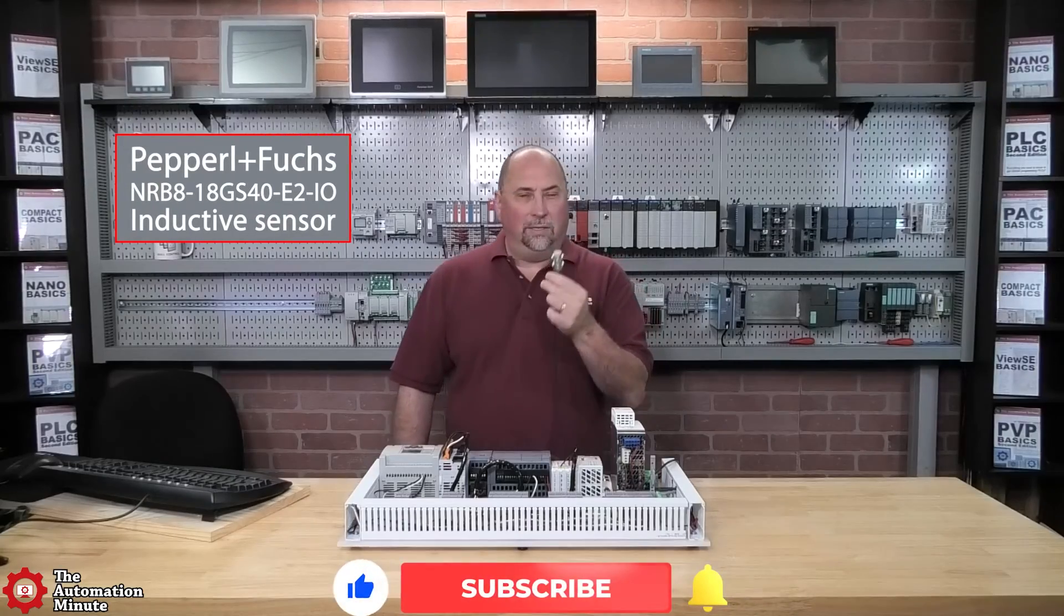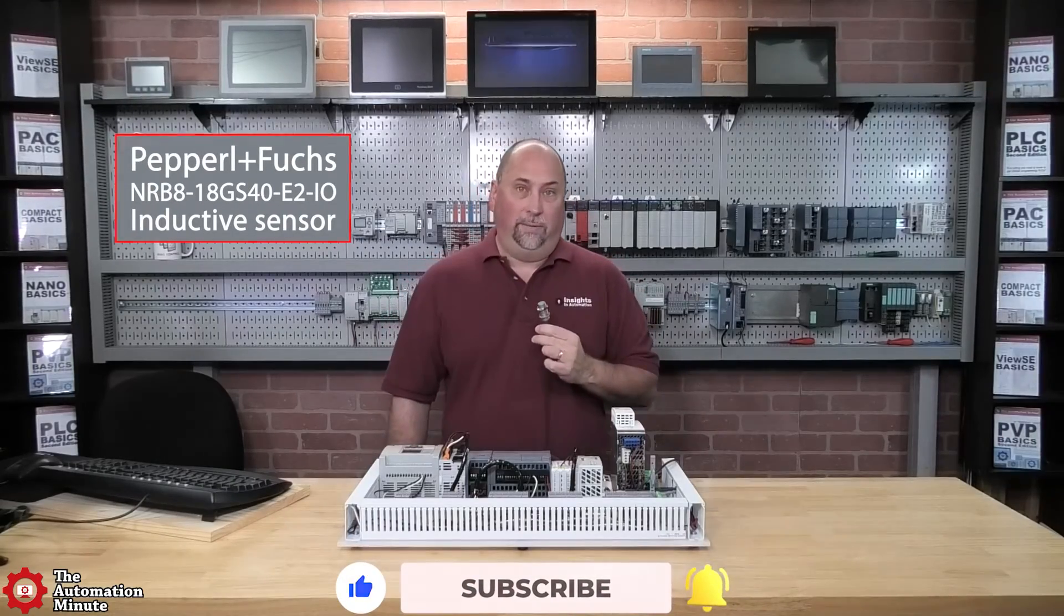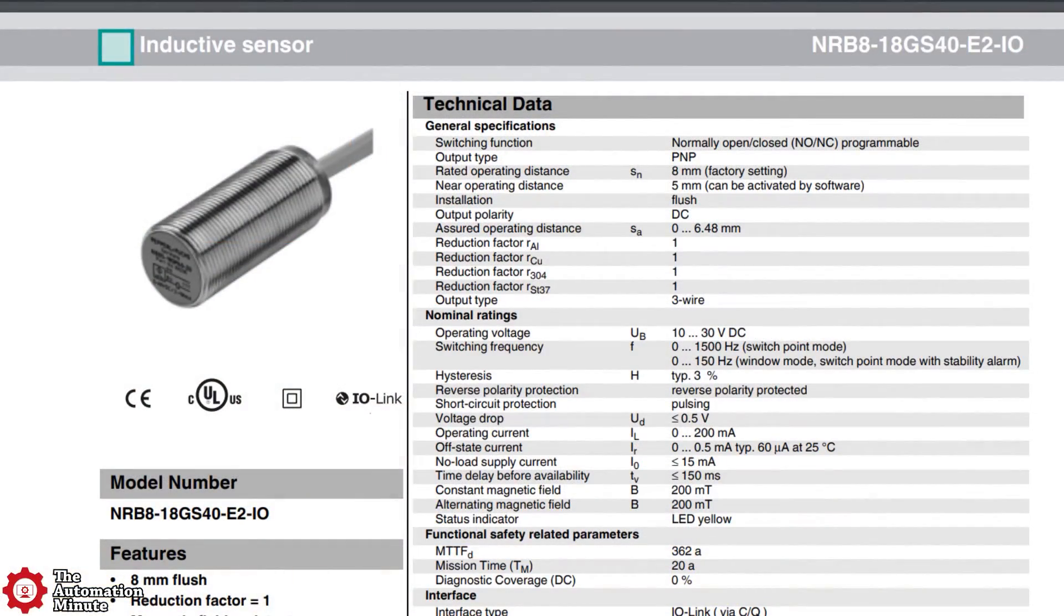Today we're taking a first look at an inductive proximity sensor from P+F, the NRB8-18GS40. It's an IO-link-enabled prox that comes with a PNP output, which defaults to normally closed but can be programmed to be normally open.